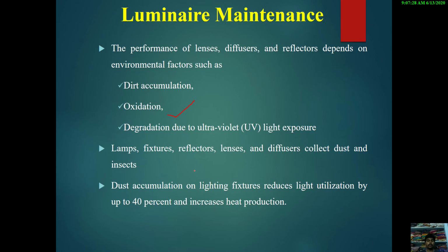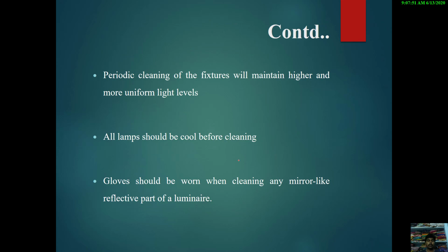will collect dust and insects, and this dust accumulation on lighting fixtures results in reducing the light utilization by up to 40% and increases the heat production, which will result in the failure of the lighting system, or will decrease the efficiency of the lighting system. And all lamps should be cooled before cleaning, and gloves should be worn when cleaning any mirror-like reflective part of a fixture, that is a fixture or luminaire.